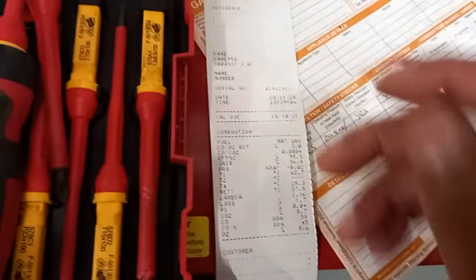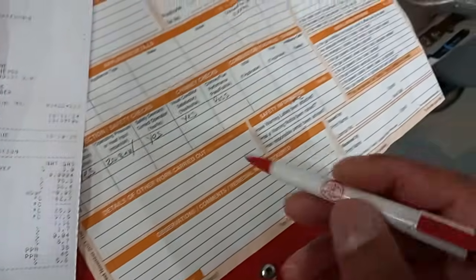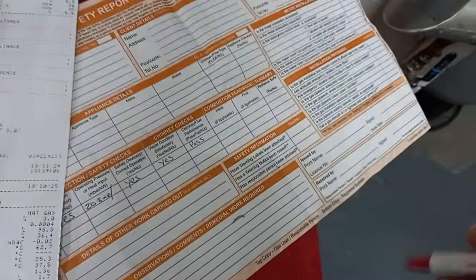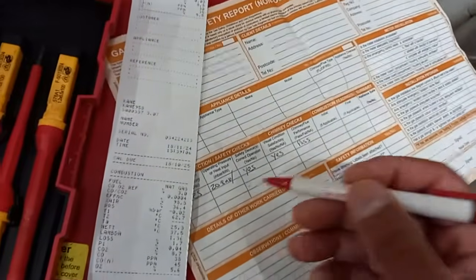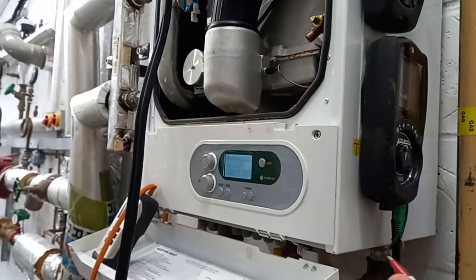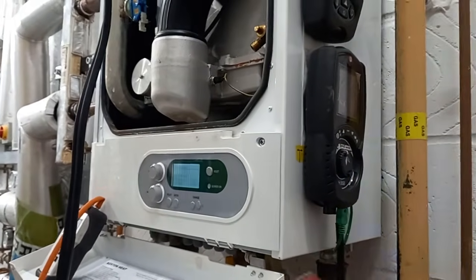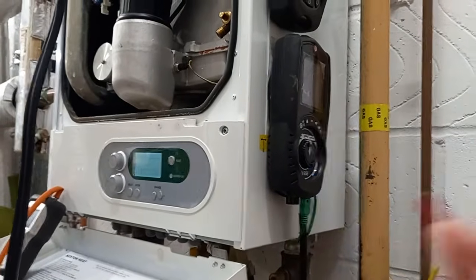For our combustion readings, we write down high and low. This particular sheet doesn't ask for the time of the safety shutoff, but some sheets do ask how long it took — for instance, 130 seconds. So bear that in mind; not every sheet is the same.